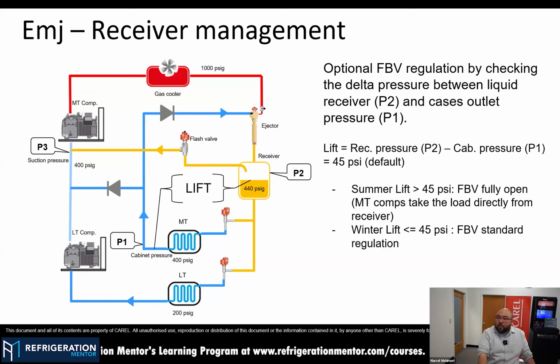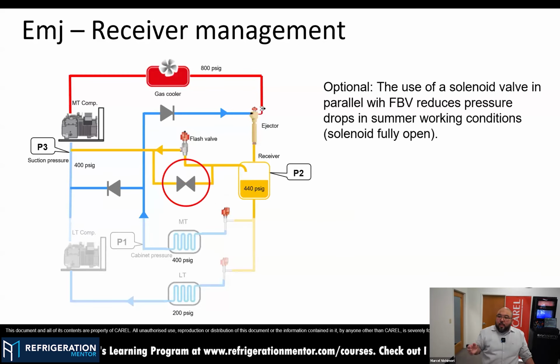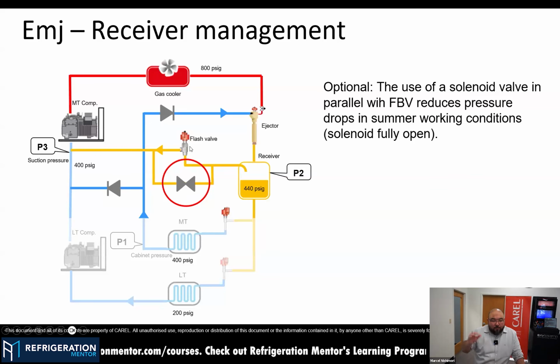Perfect. That's correct. So you can imagine that once we have the ejector effect engaged, with all the refrigerant coming from the gas cooler and all the refrigerant coming to the ejector port, the amount of CO2 vapor here at the liquid receiver will increase, right? Because you have dual sources of vapor coming from two different parts of the system. So normally, this valve, the flash gas bypass valve, during summer, will be fully open to reduce the pressure drop as much as we can here. But sometimes a valve has its limitations, so you cannot go very low in pressure drop.